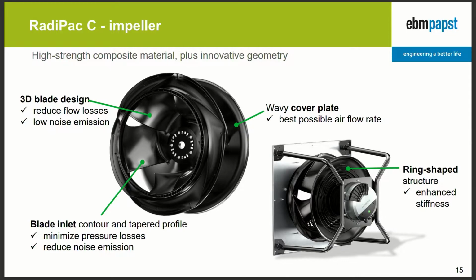So by doing it in such a way, you can create much more complicated designs. You can modify the flow path through the impeller in such a way that you have less turbulence, less changes in air velocity, and a smooth operation. Such turbulences always cause energy losses on one side, and also create noise.